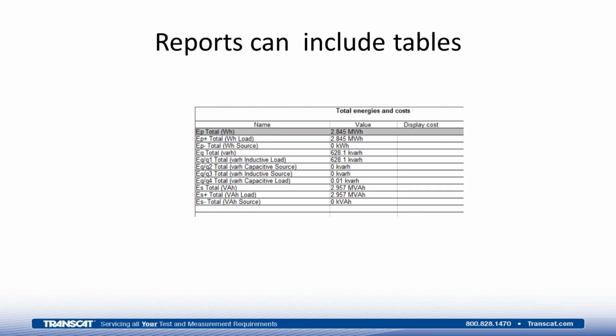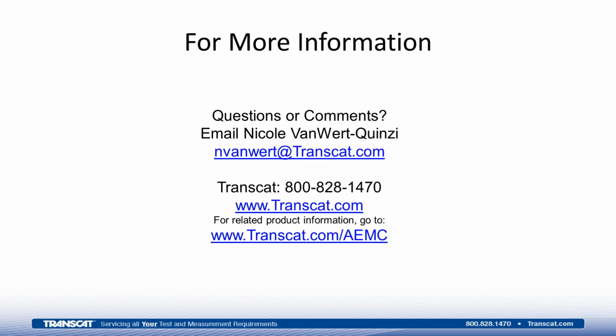From the point of view of reporting systems, you can also generate tabular reports that would document the energy information, telling you how many megawatt hours in this particular case were being used. And this could be used to relate to your energy bill. The PEL product even incorporates an ability where you can put in your energy cost in cents per kilowatt hour, even if you have multiple billing periods during the day, and it can give you the dollar value of the energy usage expressed in actual US dollars.